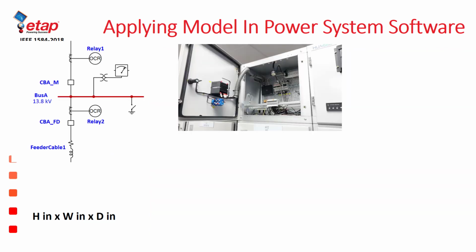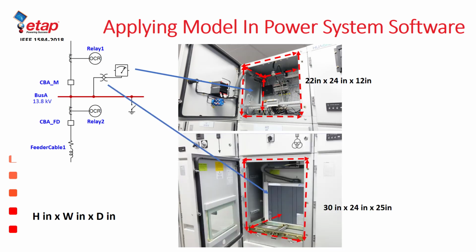Further examples of this, with the actual enclosures open, show that here is our instrumentation area, where perhaps we may not even have direct contact to the bus. Therefore, with different voltage levels, which could range from 120 to 240 volts AC, we may have different assumptions on how to calculate the energy using the new low voltage part of the model. Similarly, we can have the actual PT compartment analyzed using different enclosure sizes and different depths in the elements.